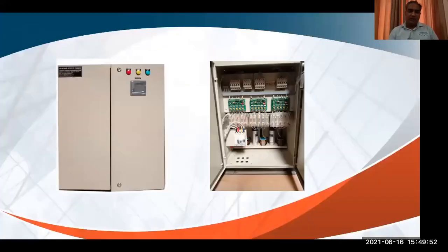So this product evolved out of the industry's need for something in a smaller package to control power factor and maintain it above 0.95, because in Rajasthan there's no incentive above 0.95, they just have to avoid penalty above 0.9. We have all the case studies in place for this panel, which is a complete end-to-end solution.